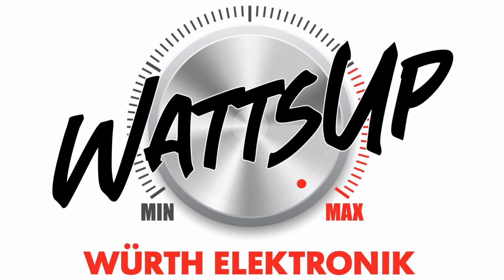And related to the rated current is the so-called derating. That means if I put my component into an ambient temperature which is above a certain limit ambient temperature, then I have to decrease the current flowing through the winding. So for mains filter chokes, mains line chokes, the limit is normally 70 degrees Celsius, because we have a maximum operating temperature of our components of 125 degrees Celsius. And for 55 Kelvin, then it's just a difference.